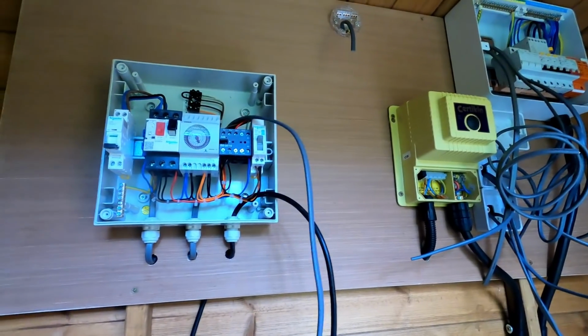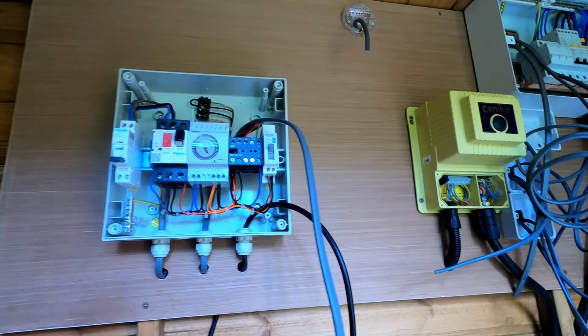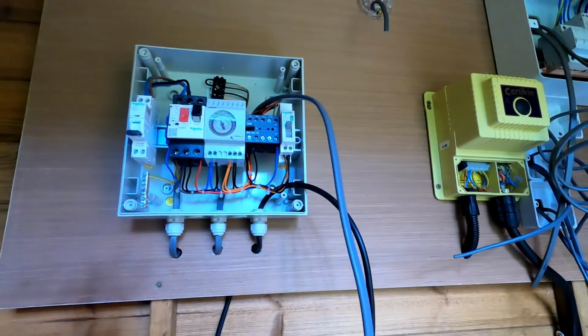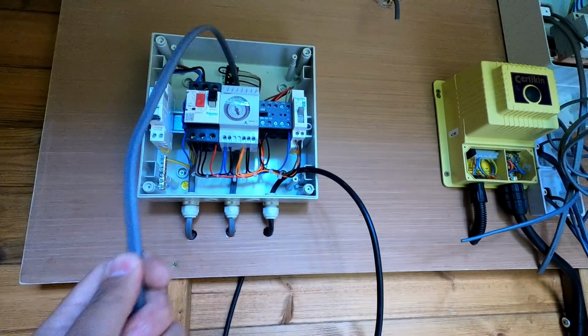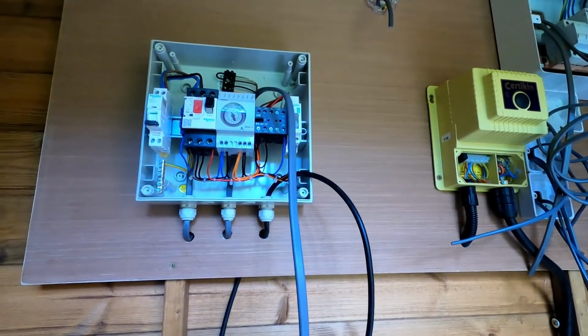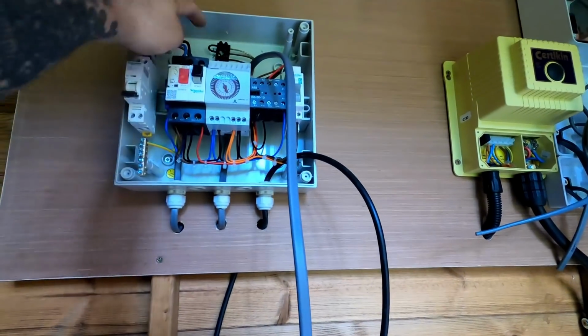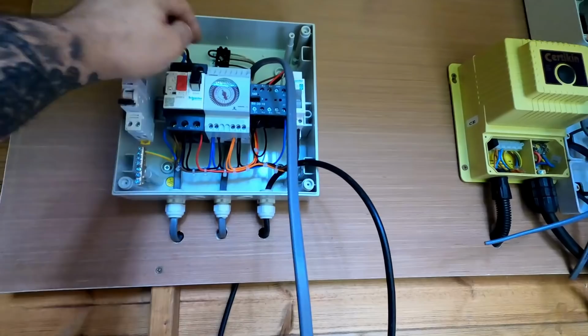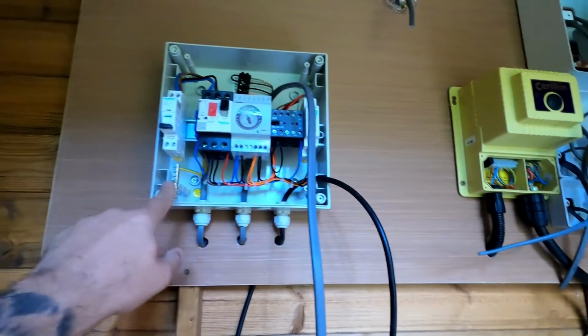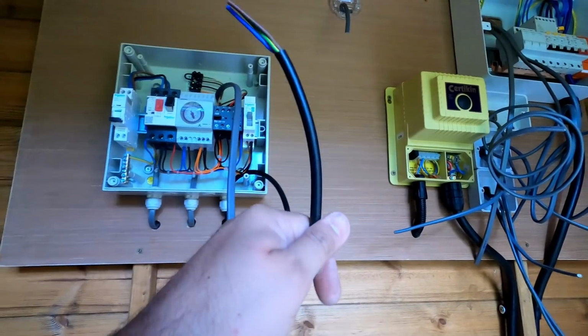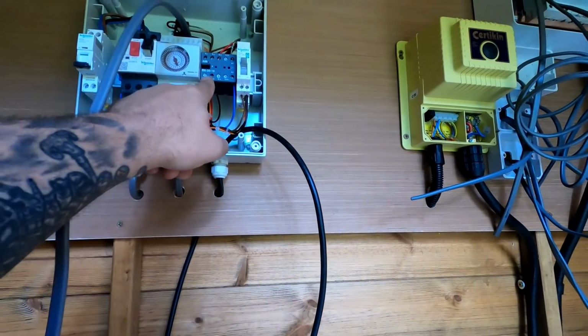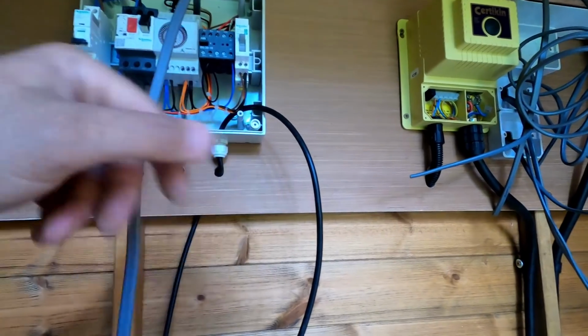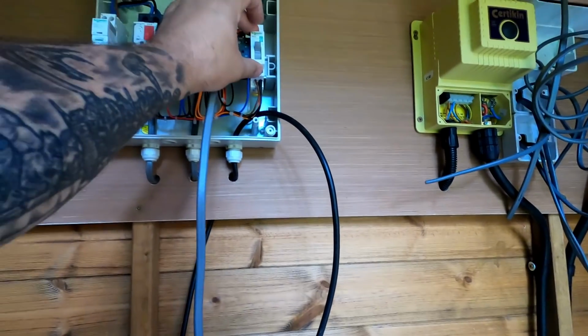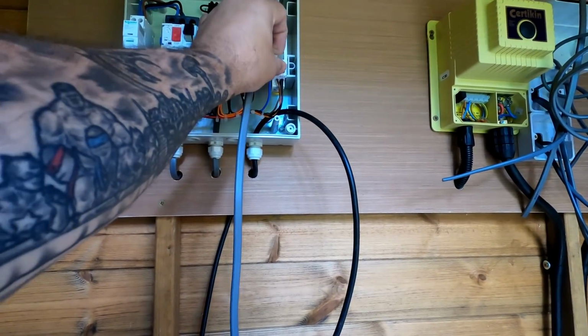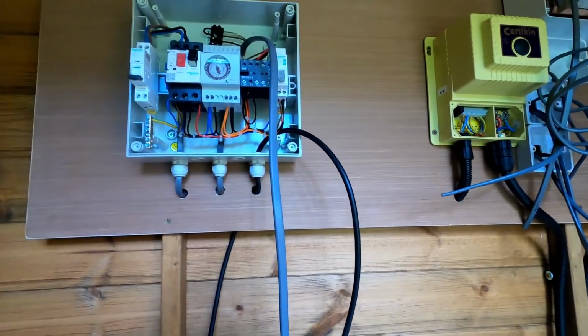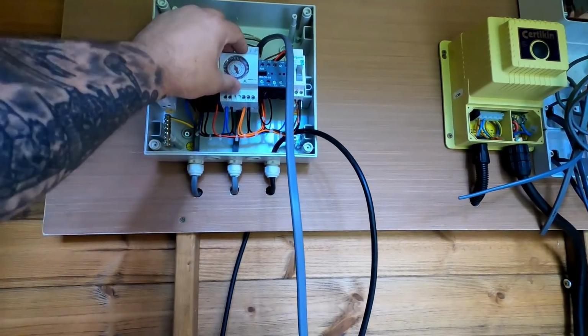I'm just waiting for a call back from the pool guy, because nowhere in the instructions does it say where to fit the actual heat source exchange. It's got anti-frost and low contact, which is probably going to be that. But best to get clarification. But ports 3 and 4, so that'll go up there. Earth bar there, and then we've got our pump feed here, which basically connects into 2 and 6. So the CPC will go over to there, and then you basically have a timer, off, and manual. So it's going to be set to timer once we've got it all up and running.